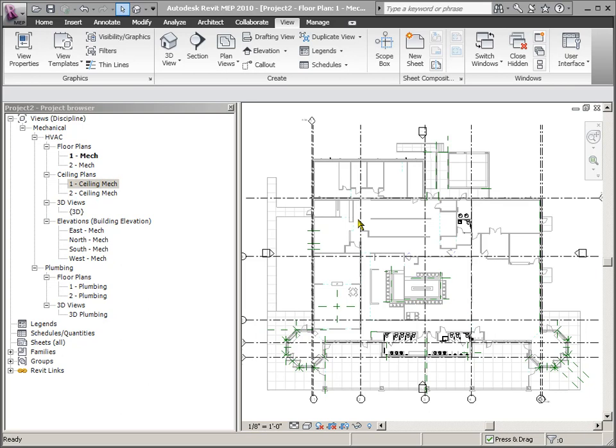An engineer's regular ceiling plan is from the perspective of a person looking down. You're standing above the level, looking down through the level, so you see the ductwork first above the ceiling grid, also above your diffusers, so the ductwork hides the diffuser.